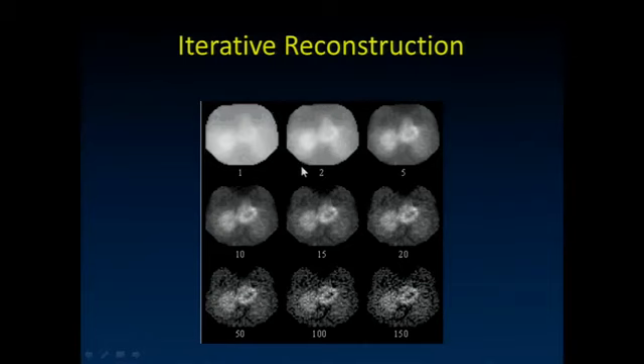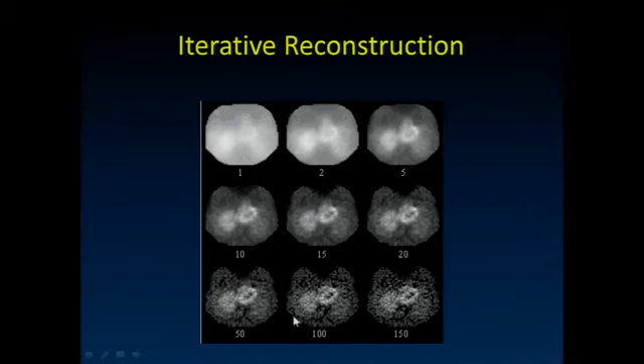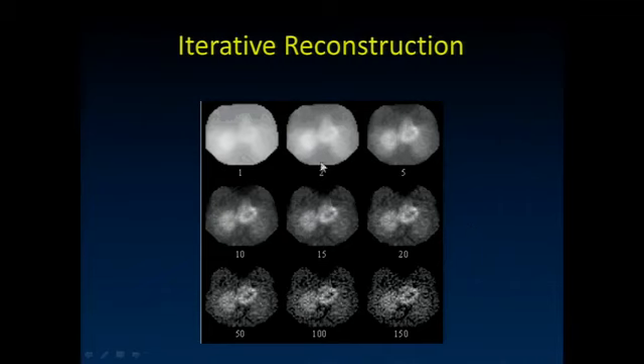We first used iterative reconstruction in nuclear medicine. Here's a cardiac study showing the entire chest. Here are the number of iterations: 1, 2, 5, 10, 15, 20, 50, 100, 150. As you continue to iterate, the data tends to get noisier and noisier—you amplify noise with more iterations. So you've got to pick your stopping point. When I ask people which image looks best, there's quite a bit of variation; some say stop at 10, others at 20. But people mostly pick something in that middle row.